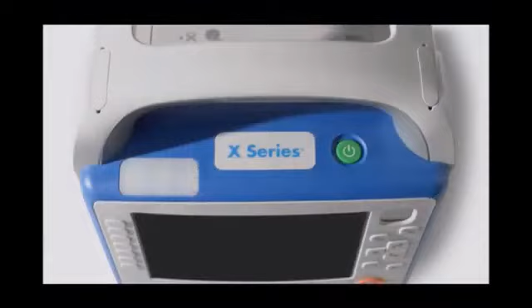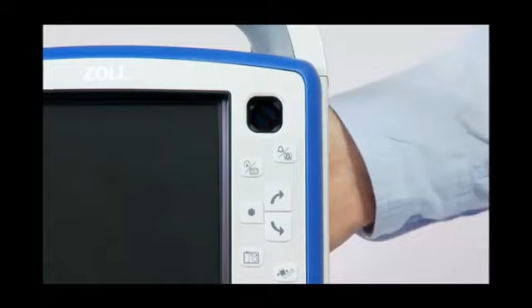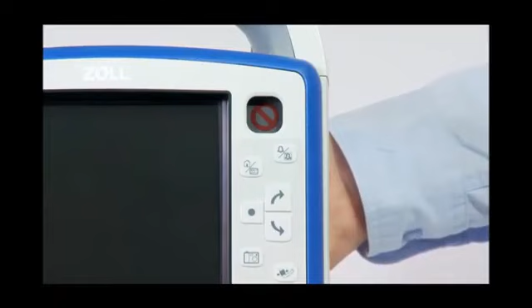The RFU indicator gives you an immediate indication if the device is ready for use without turning on the monitor or waiting for power up. It shows the status of the unit based on the most recent readiness check. A black circle indicates the unit is ready. A red circle with a line through it indicates that the unit's readiness has been compromised and that it may not be ready for therapeutic use.